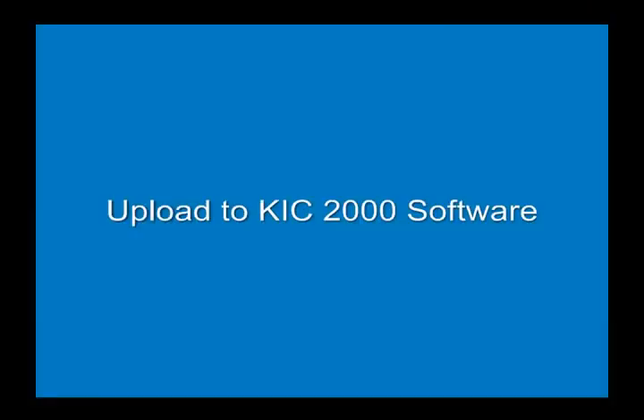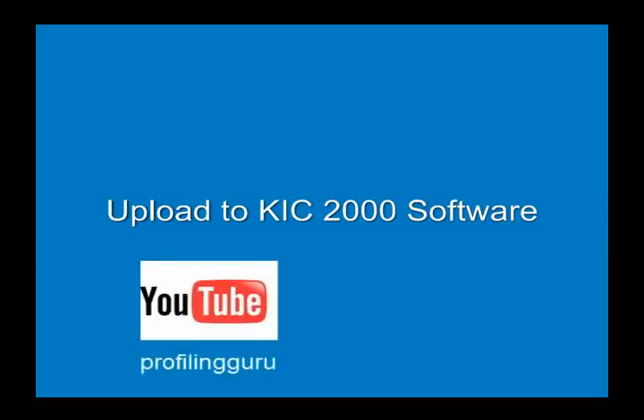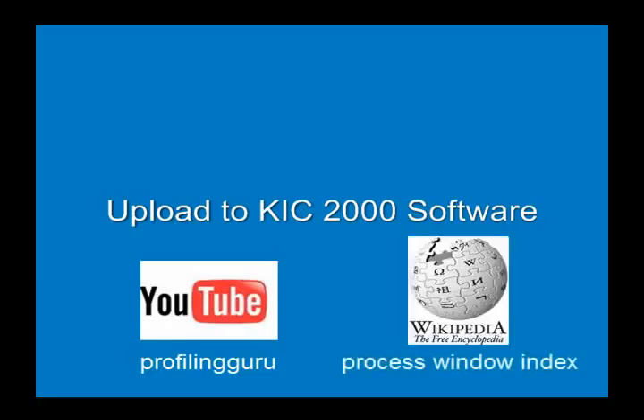In this example, I'm uploading profiling data using KIC 2000 software. I'll be using the Process Window Index, or PWI. If you are not familiar with PWI, you can find out more at Profiling Guru on YouTube or simply enter Process Window Index in Wikipedia.